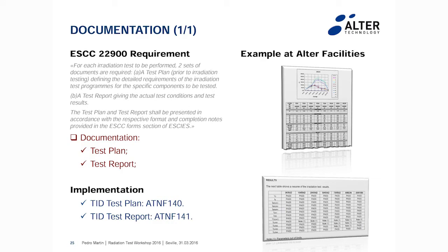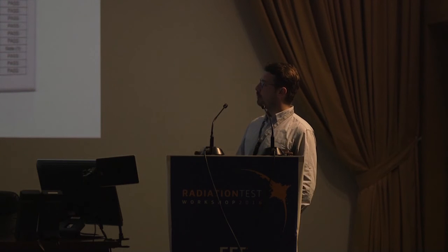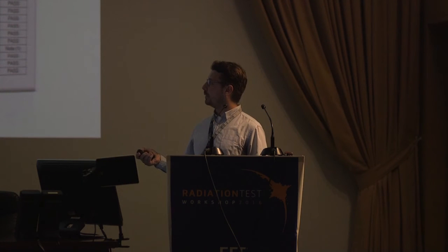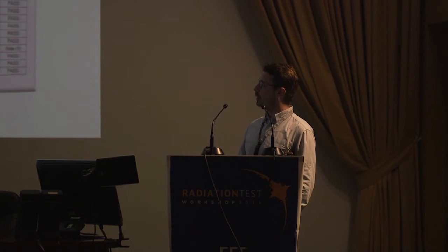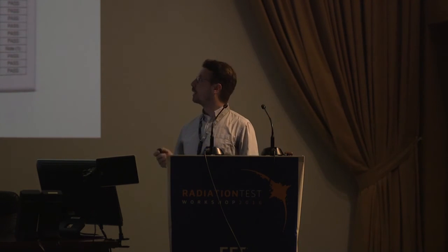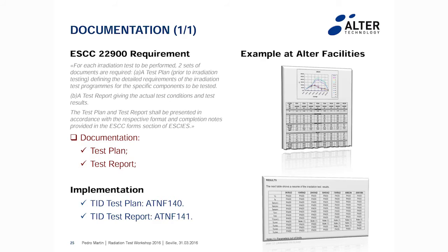About the documentation, there are no specific and difficult requirements, but we have to say that a test plan is required, approved before starting the test, and of course a final test report which contains all the graphs and results obtained during the test.